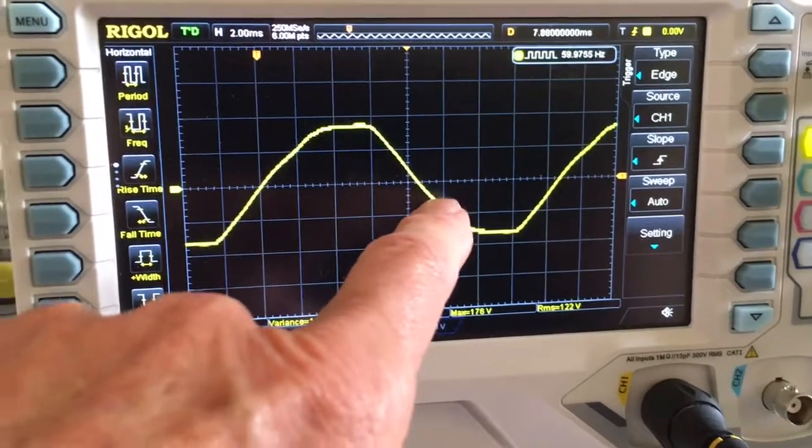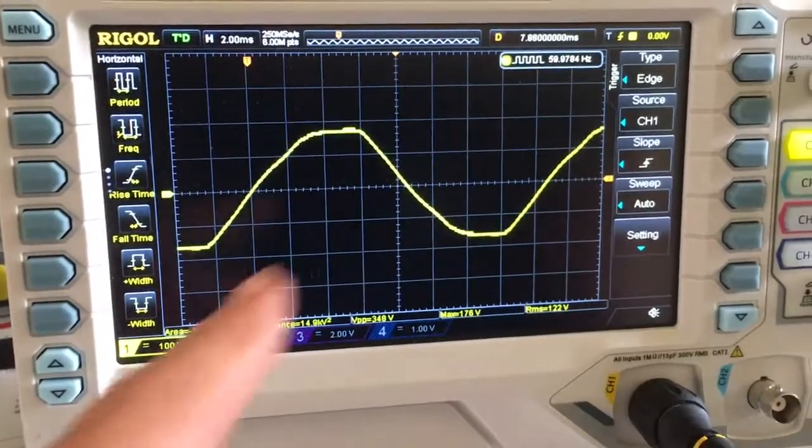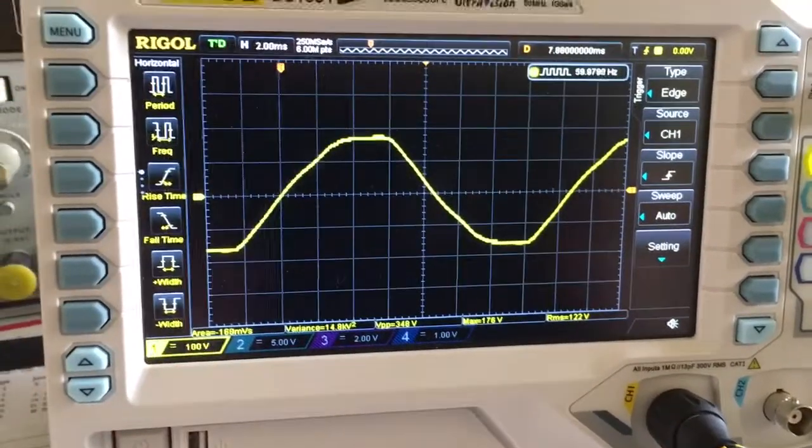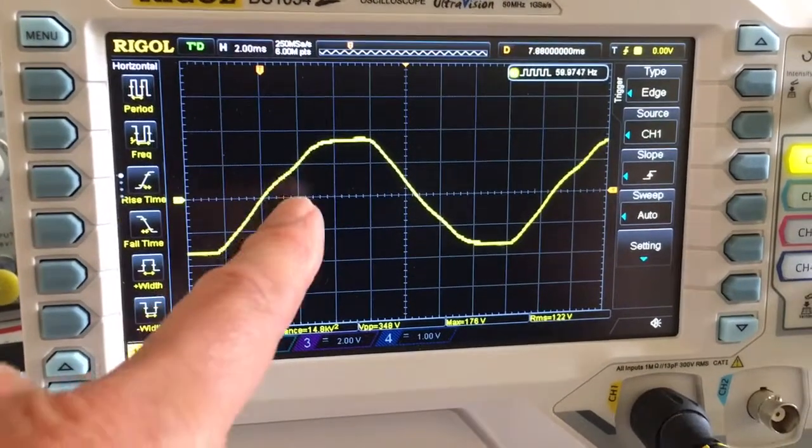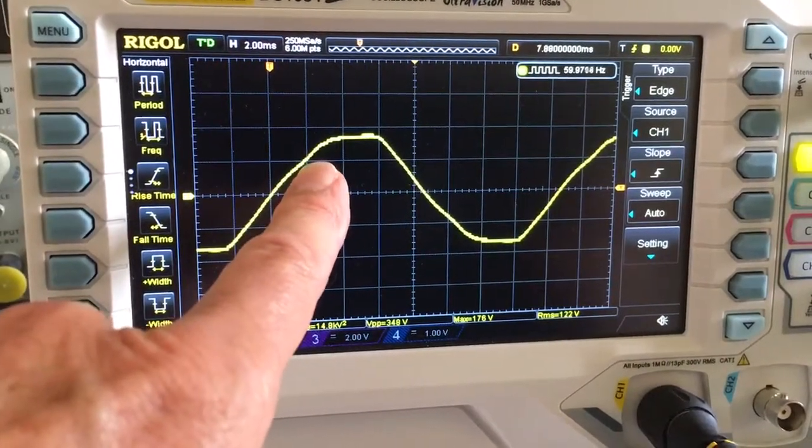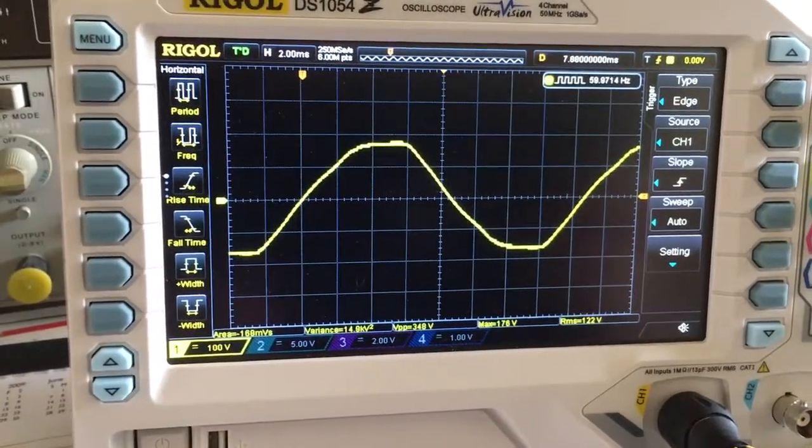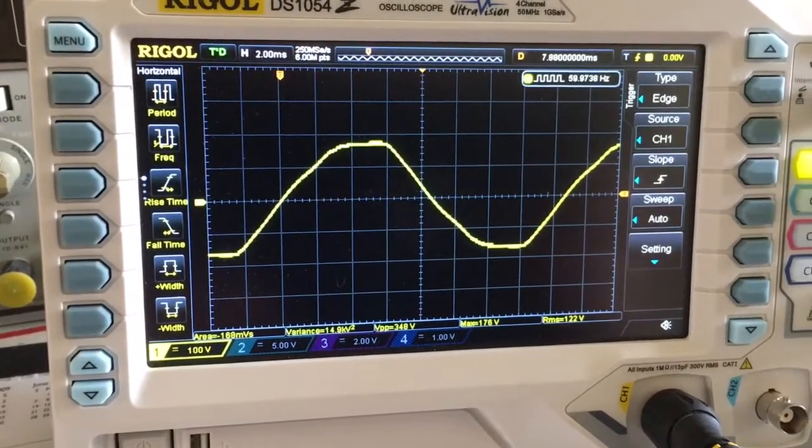My meter, if it responds, will make a small glitch here and here. It's a very high frequency glitch, but the outgoing signaling from the substation is low frequency. It's this very small thing you see here. That looks small, but we're on 100 volts per division, so it's bigger than you think.